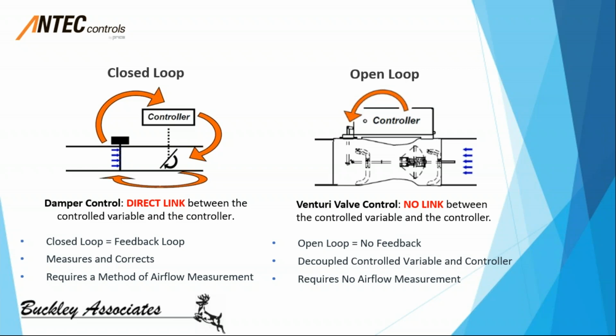So this sensor sends a signal to the controller that controls a damper that then reacts and varies the airflow. Okay, so then the sensor again measures the airflow, sends a signal to the controller. The controller then moves the damper, and you see how we have this signal here where we have a closed control loop, and it goes on and on and on. A lot of times we call this a feedback loop. We're always going to measure this flow and then correct the flow.